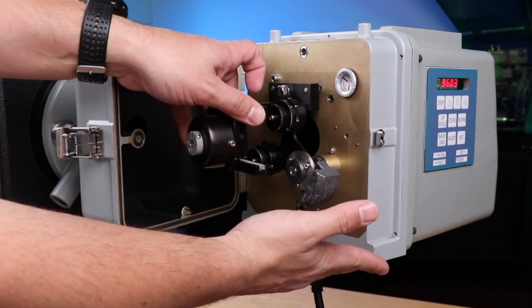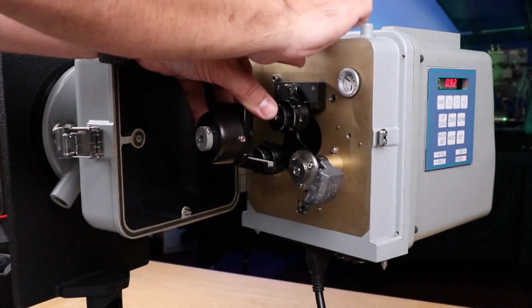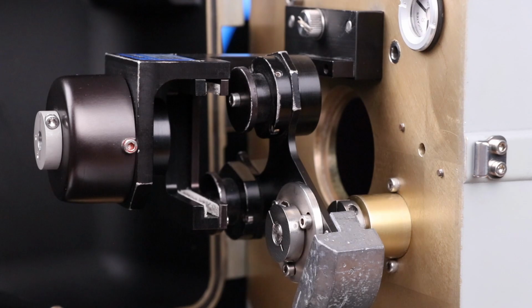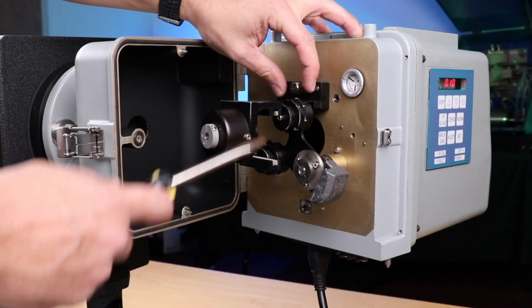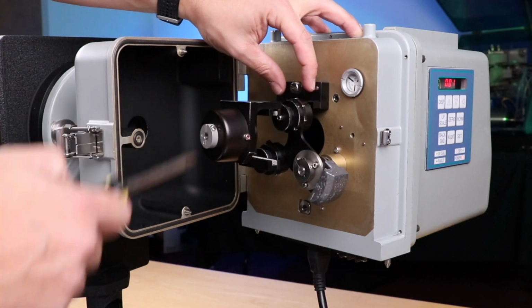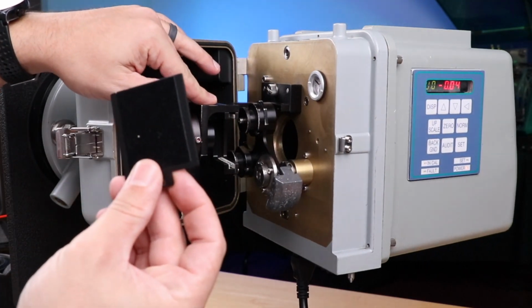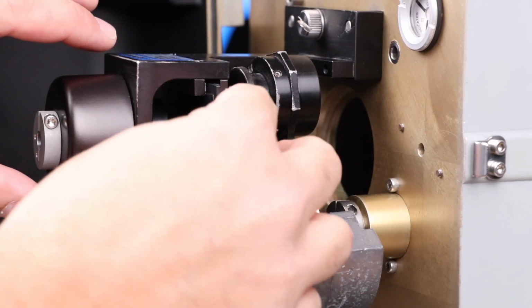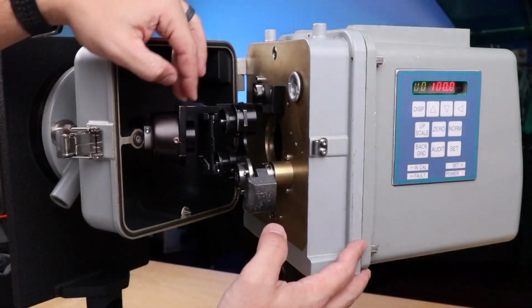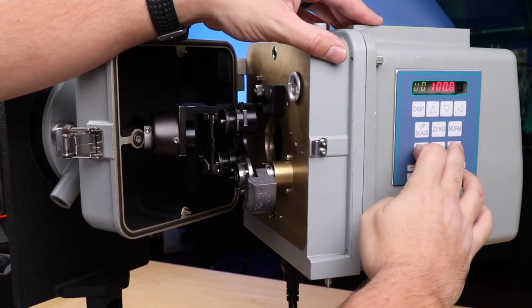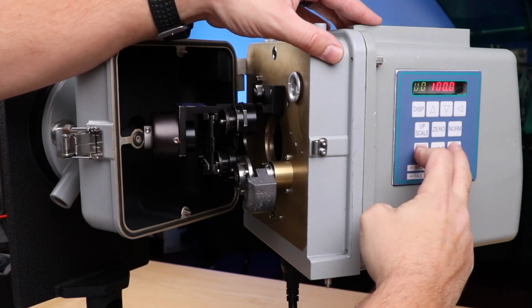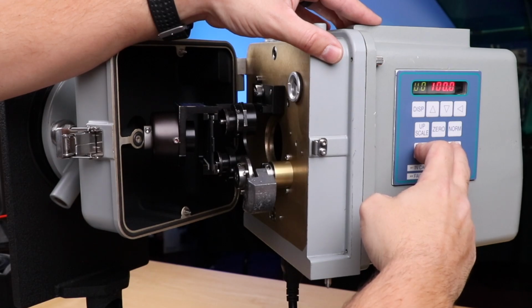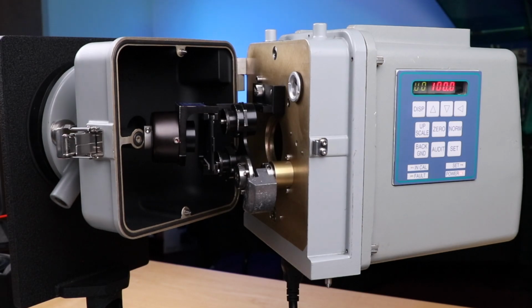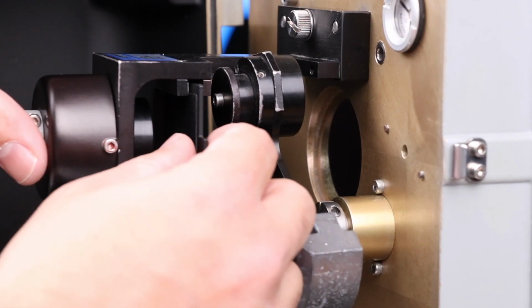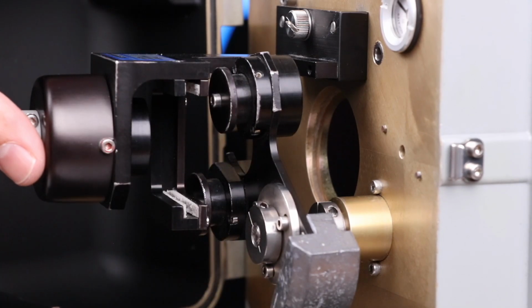Install the cal fixture to the optical head assembly. Be sure the fixture sits flush against the face of the optical head. Gently tighten the screw to ensure the fixture stays in place. Create 100% opacity by inserting the blocking plate. Then initiate the background set by holding Set and Background until the set light flashes 5 times and goes solid. The background set will take about 6 minutes. Once the set light goes out, remove the blocking plate.